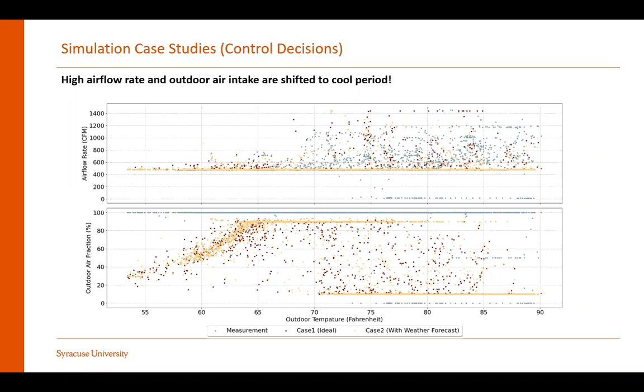The fresh air intake is controlled more intelligently by our advanced control strategy: recirculated air dominates when the outdoor air temperature is hot, and when conditions are favorable we introduce more fresh air into the room. When the outdoor air temperature is lower than 65 Fahrenheit, the fresh air intake is adjusted dynamically to leverage free cooling, which is where the significant load reduction comes from.